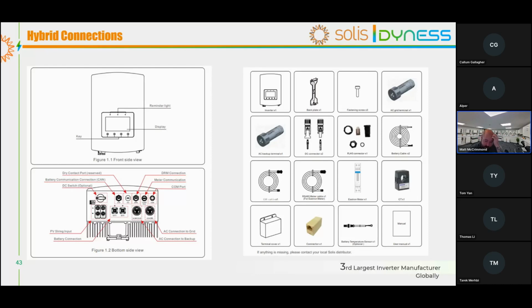We then have the meter. In the box that comes with the S5, we actually supply you with an Eastron single phase meter, which you can RS485 back to our inverter, which is where we get the communication and how we monitor what's happening at the grid. We also have the CAN port, which is massively important, especially in collaborations with the likes of Dyness, because ultimately our inverter has to work with the battery. And when I say work with the battery, we are effectively a slave to the battery.